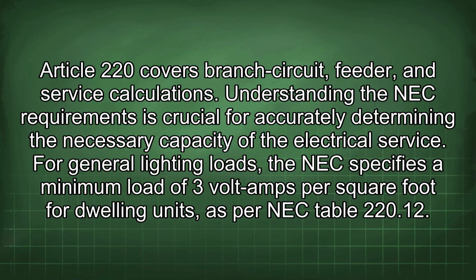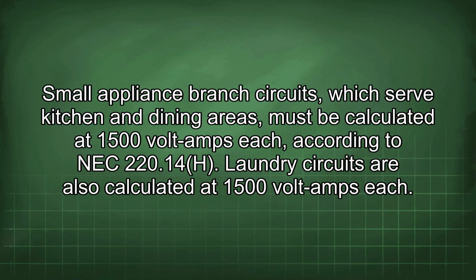For general lighting loads, the NEC specifies a minimum load of 3 volt-amps per square foot for dwelling units, as per NEC Table 220.12. Small appliance branch circuits, which serve kitchen and dining areas, must be calculated at 1500 volt-amps each, according to NEC 220.52. Laundry circuits are also calculated at 1500 volt-amps each.